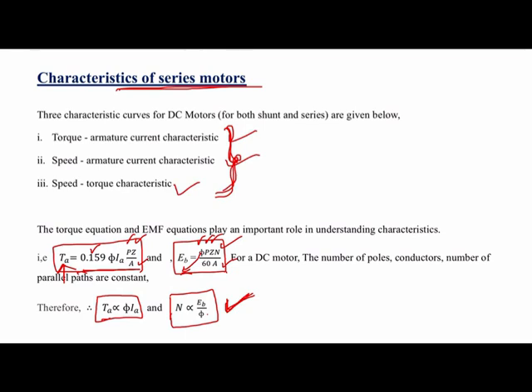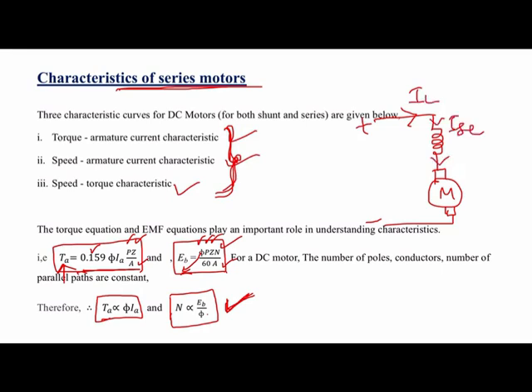One important thing to remember about the DC series motor: the field winding is connected in series with the armature. Because of this series connection, the line current IL, the series field current ISE, and the armature current IA are all equal.